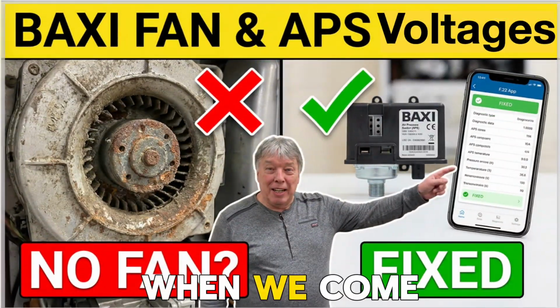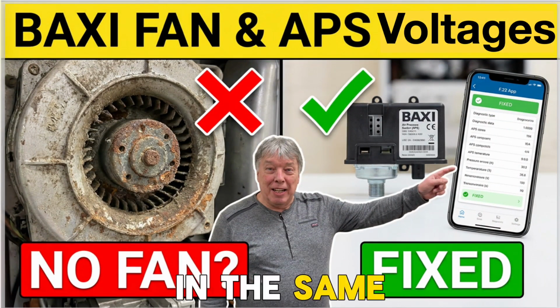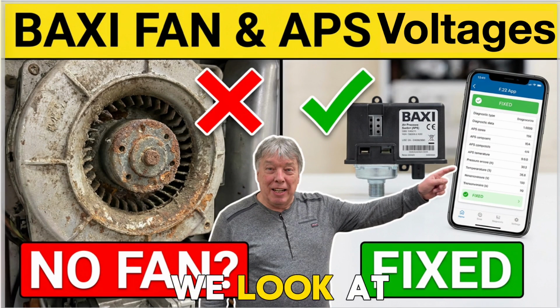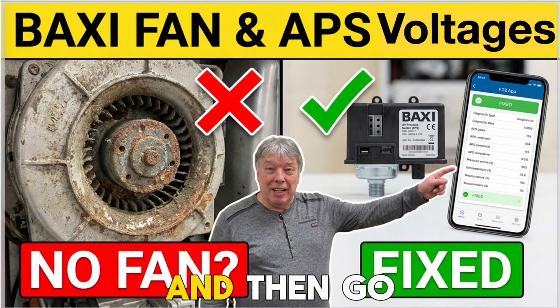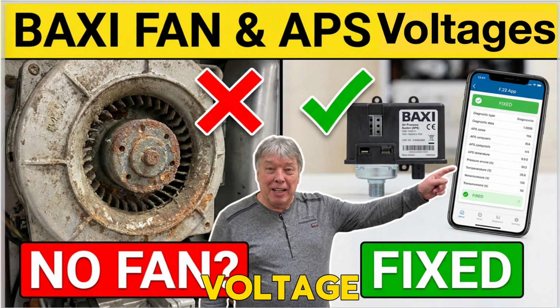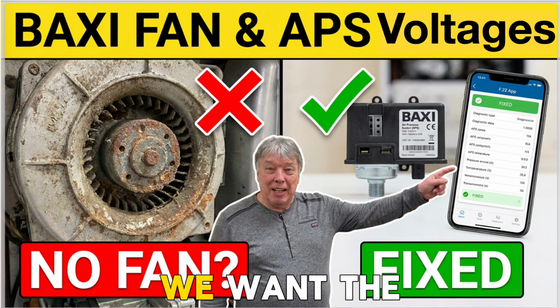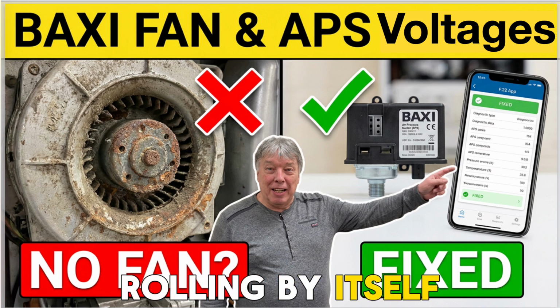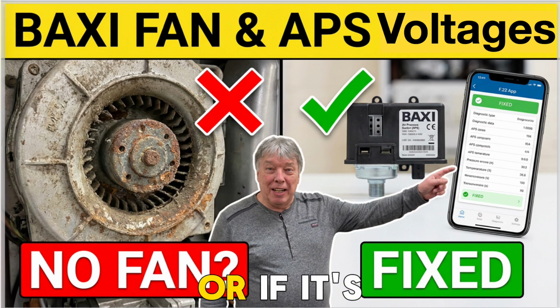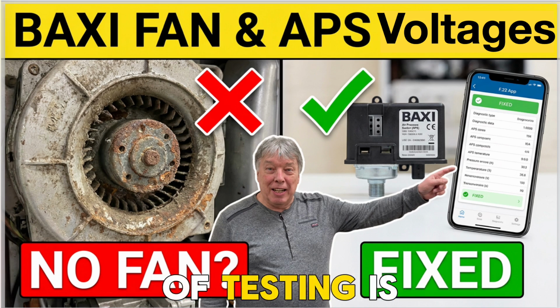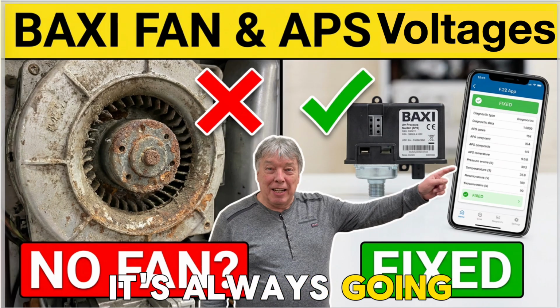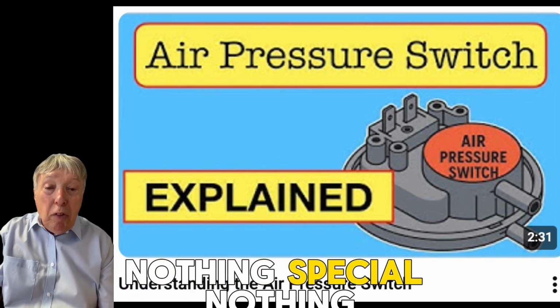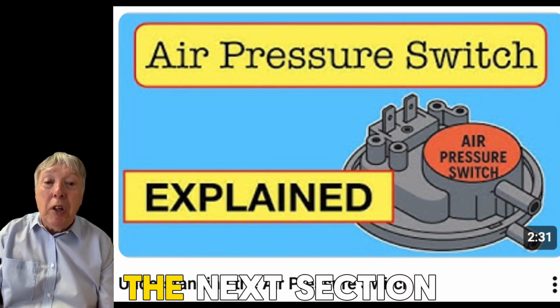When we come to testing the fan, we do that in the same procedures we test everything else. We look at the voltage on the PCB and then go to the fan terminals and measure that voltage that it's arrived, so the wire's not broken. Don't spin the fan because that's cheating. We want the fan to start rolling by itself as soon as it gets 230 volts, or if it's a DC fan, the procedure of testing is the same. So after the fan runs, it's always going to be an air pressure switch or sensors. So we test those in the same normal way. Nothing special, nothing difficult. So we can move on to the next section after testing the fan.